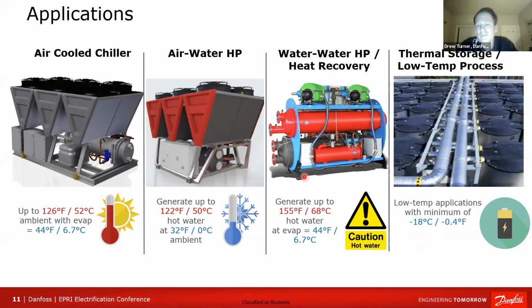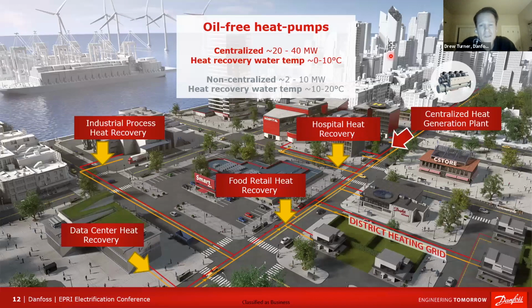But what we're especially focused on is these water-to-water heat pumps. There are several reasons for that, but I'll talk a little bit more about the detail on that. Tied to the trend to heat pumps, as I'm sure you heard about last week and several other times as a part of these EHPA webinars, is the need for thermal storage, both cooling storage as well as heating storage. It's the same ultimate driver of integrating more renewables that drives the need for this as well. And we now have that capability. But what we're specifically focused on is the district heating market and water-to-water heat pump applications.